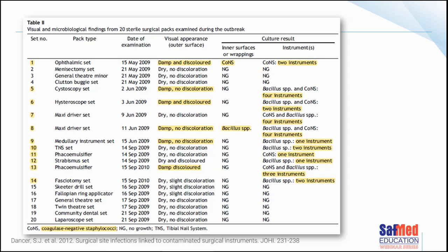Set number five was damp but with no discolouration — positive. Set number six was damp and discoloured — positive. Set number seven was dry with no discolouration, yet there were still microorganisms on the instruments. So in some instances, the sets were dry and not discoloured, yet they were still positive for microorganisms.